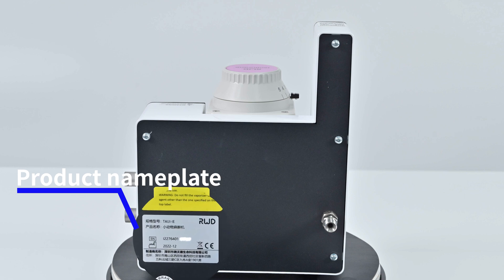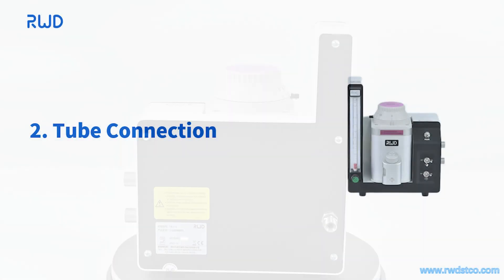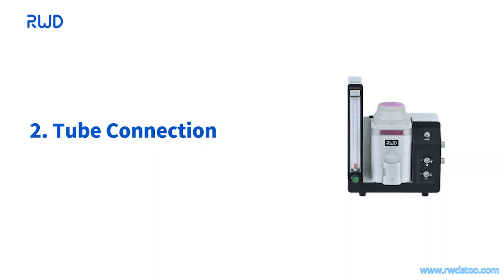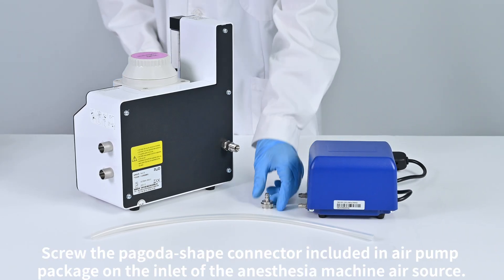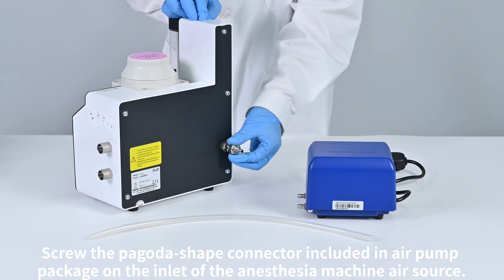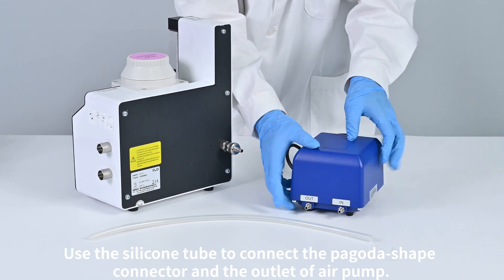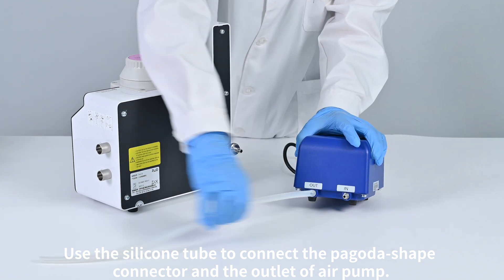Product nameplate. Air inlet. Air pump connection: screw the pagoda-shape connector included in the air pump package onto the inlet of the anesthesia machine air source. Use the silicone tube to connect the pagoda-shape connector and the outlet of the air pump.